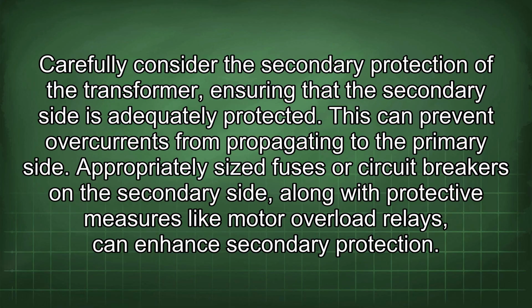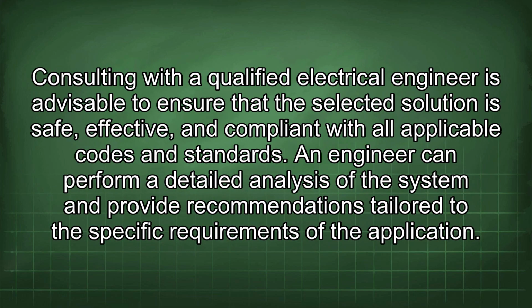Appropriately sized fuses or circuit breakers on the secondary side, along with protective measures like motor overload relays, can enhance secondary protection. Consulting with a qualified electrical engineer is advisable to ensure that the selected solution is safe, effective, and compliant with all applicable codes and standards. An engineer can perform a detailed analysis of the system and provide recommendations tailored to the specific requirements of the application.